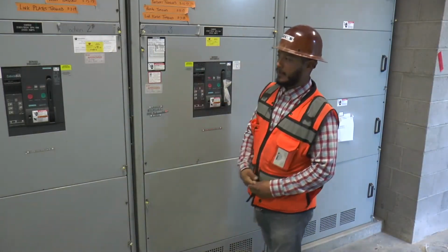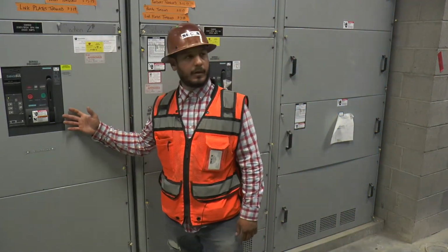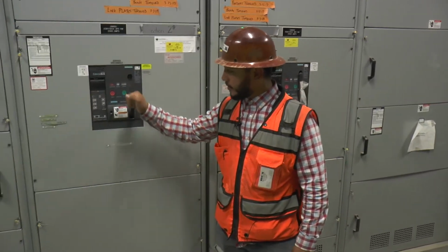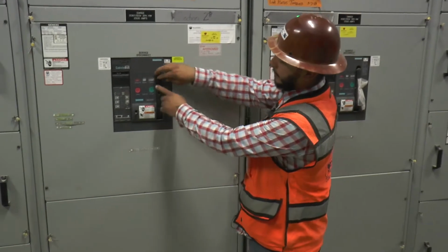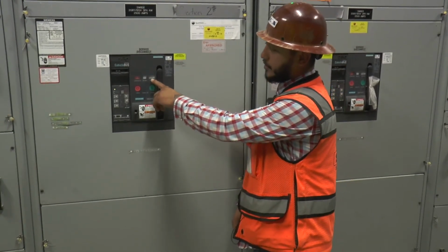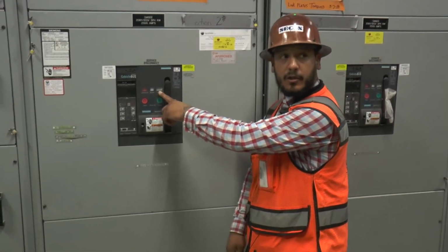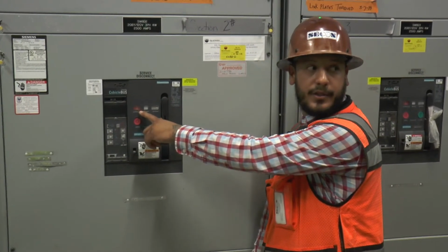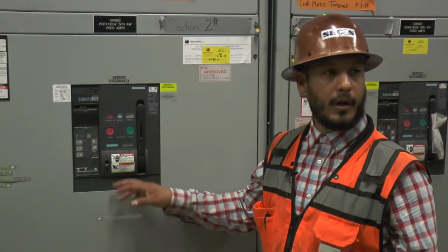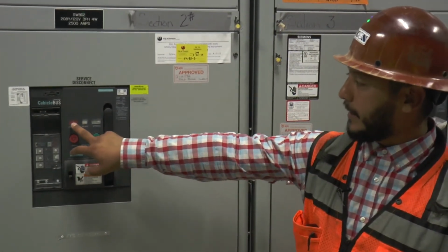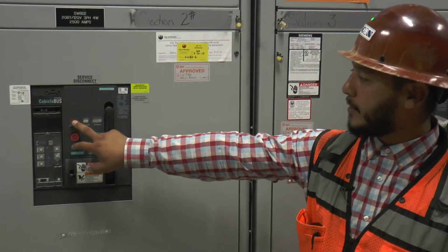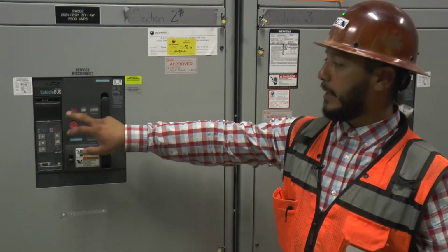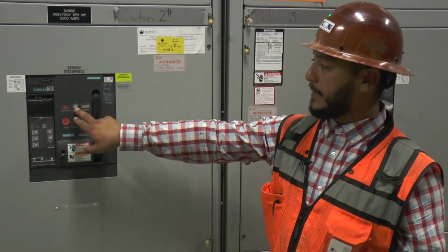In case of any faults or tripping on this breaker, you would have to pull this lever to keep charging it. This will indicate a window here telling you that it's charged or discharged. Right now it's in the discharge position because it will not let you charge it again, because we are in the closed position. The circuit is closed. We have live power. This will indicate if it's tripped or if somebody just simply opened the circuit. So it'll indicate both. And then the ready will tell you it's okay.